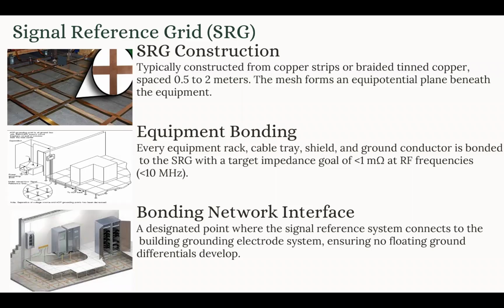And the bonding network, the equipment bonding, also has some requirements. One is that every equipment rack or cable tray or shield and ground conductor should be directly bonded to the SRG. It should use short wide bonding straps so we can reduce the inductance. The purpose is to prevent differential ground potential between the equipment, which can basically cause common mode noise on the signal lines. We also have to have a bonding network interface, and the SRG must connect to the building ground electrode at a single designated point.